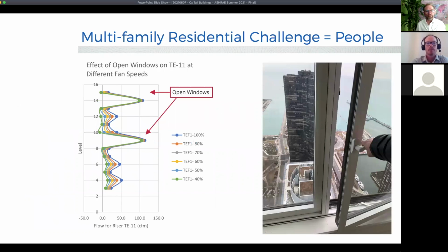And as I mentioned, with multifamily, operable windows can be a deficit to you, because now your challenge isn't automation, it isn't a PID loop, it's a person that has a hand that can open a window. And they can cause real big fluctuations in your building. This is an example of a building where we had odor complaints from cannabis or cigarette smoke. You're not supposed to smoke in the building, but people do. And the way they get away with it is they open their window and think that nobody's going to notice. And when it's really, really cold out, because they don't want to go outside on their patio or balcony, they'll open the window.